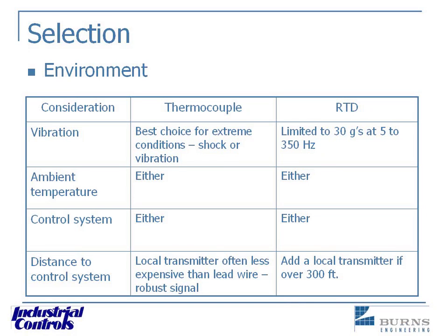Now, if you take a standard RTD and place it in a thermal well, and place that inside, let's say, a water line, that water line vibration is not going to be an issue. Would you agree? We're talking about something that's got some real high vibration. That's going to be a real issue here. To a certain extent, putting it in a thermal well and beefing it up, adding more mass and weight, tends to dampen some of the vibration. And certainly, if you do have that type of application where there is a lot of vibration, having a robust thermal well to put the sensor in is definitely a good thing to do. Ah, very good. Good point.